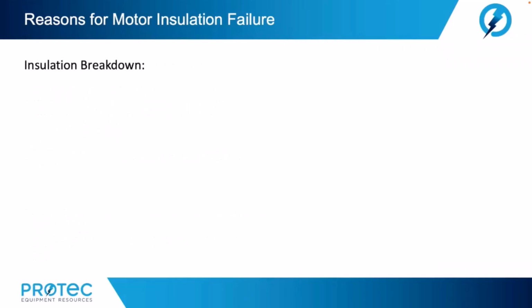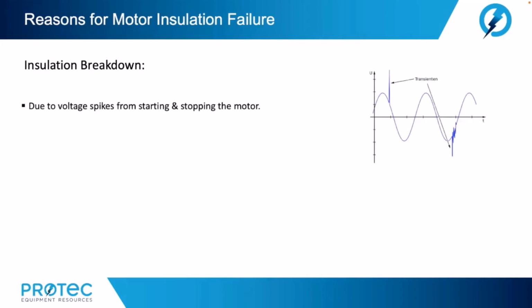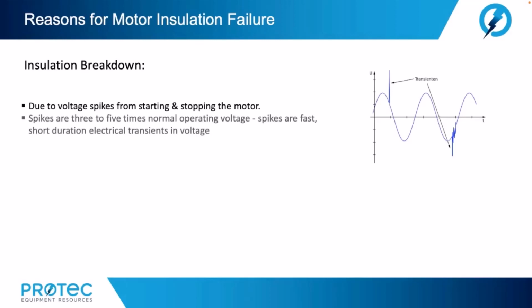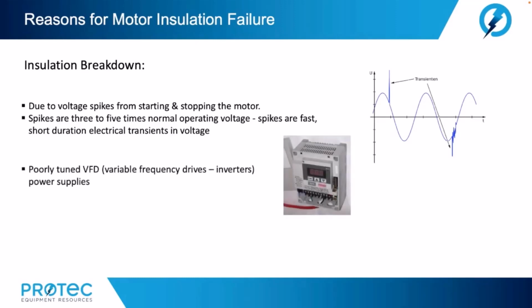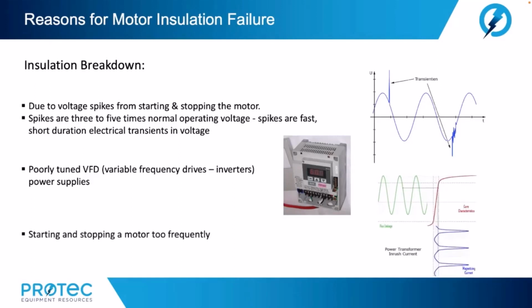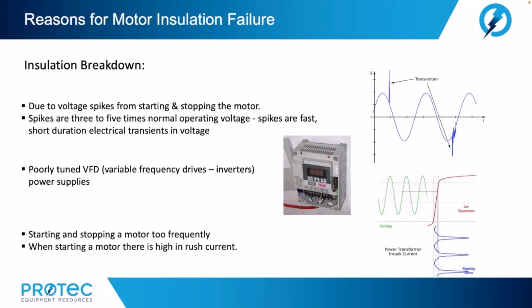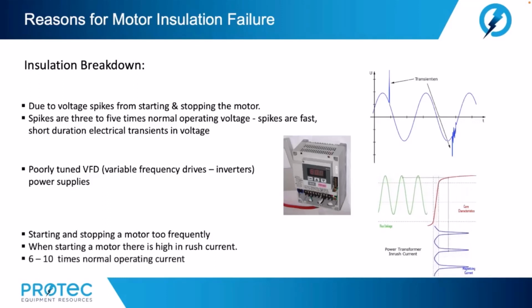All right, let's look at insulation breakdown. Breakdown can occur due to voltage spikes from starting and stopping the motor. Spikes are 3 to 5 times normal operating voltage. The spikes are fast, short-duration electrical transients in voltage. Now, this could be because of poorly tuned variable frequency drive power supplies. Also, starting and stopping a motor too frequently. When starting a motor, there is a high inrush current, 6 to 10 times normal operating current.